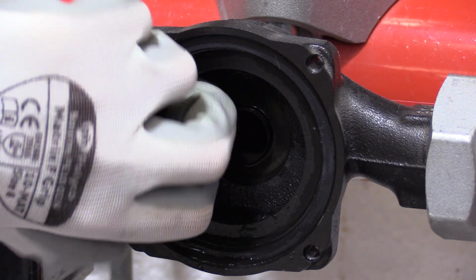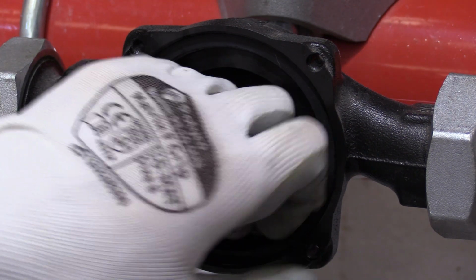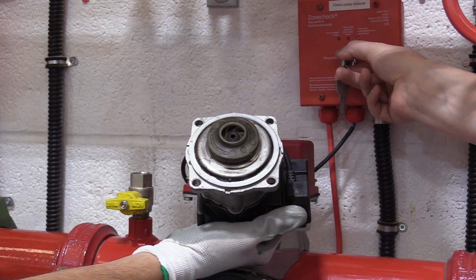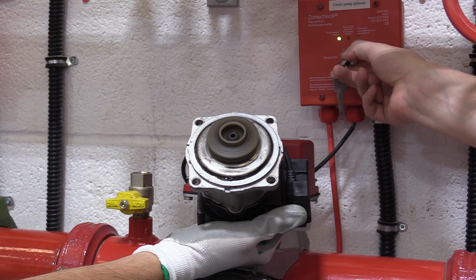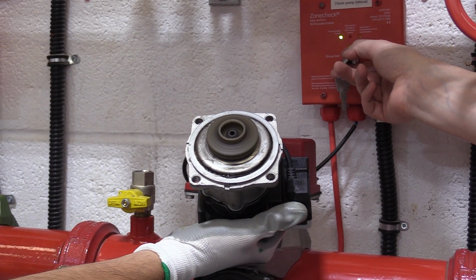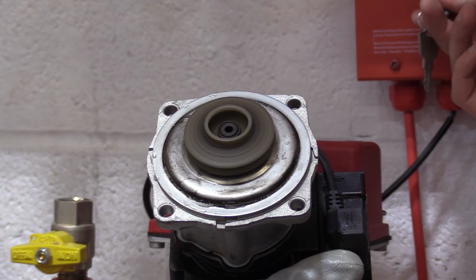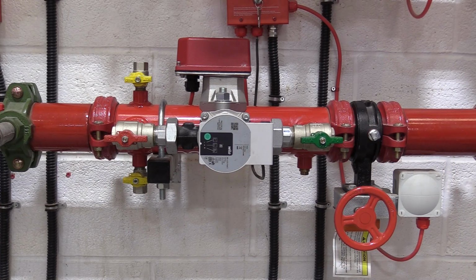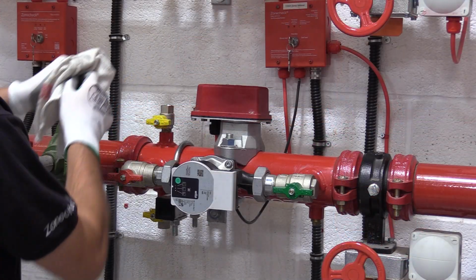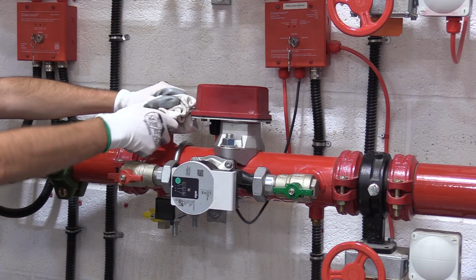Check the impeller and the pump casting for any signs of blockages and debris. With appropriate care, the pump can be run at this point to further check for free movement. Once the check has been completed, the pump head can be reattached to the casting. Note, the orientation of the pump is not critical. It is important that the pump be fully vented after reinstallation.